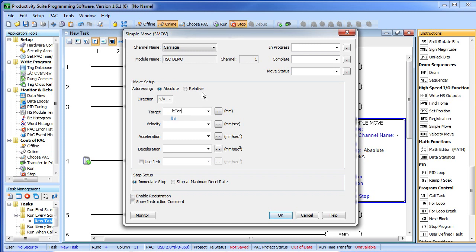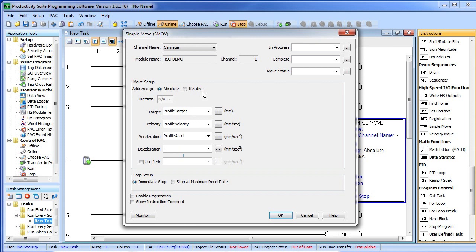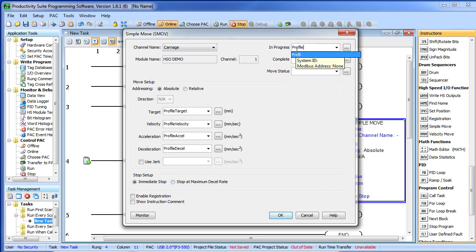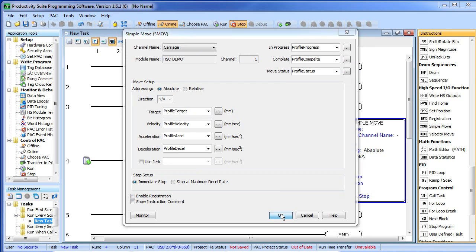This will be our profile target and our profile velocity and our profile acceleration and our profile deceleration. This jerk parameter allows you to change these linear ramps into something that looks more like an S-curve profile. We don't need that right now but check out the help file if you want to learn more about it. When we disable the instruction, I want this thing to come to an immediate stop rather than decelerate to a stop and let's go ahead and create some tags for these guys. This will be our profile progress, our profile complete and our profile status. Looks like we are good so we hit OK.